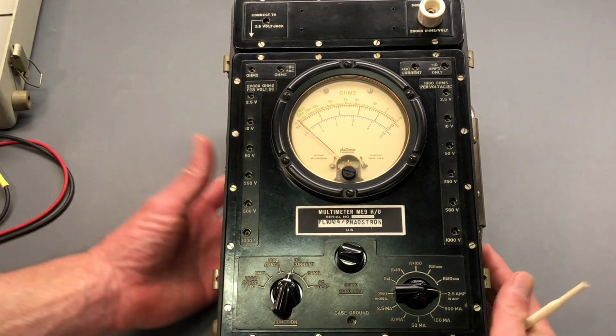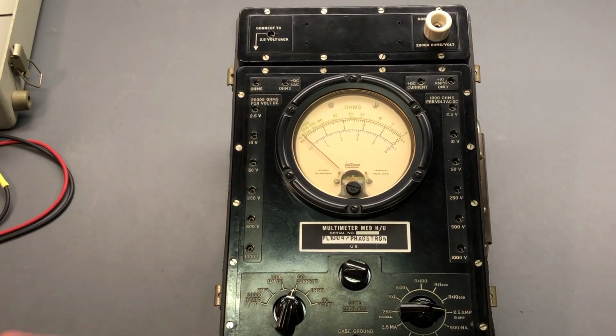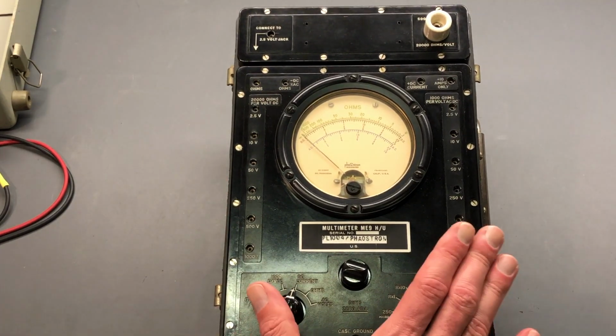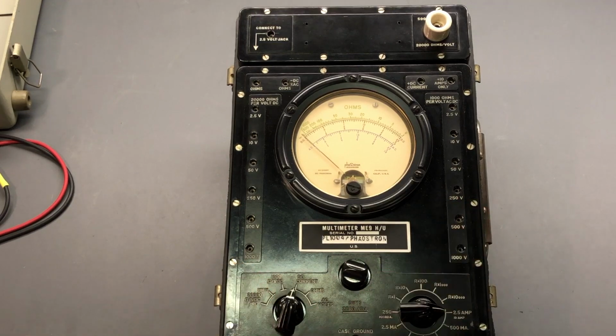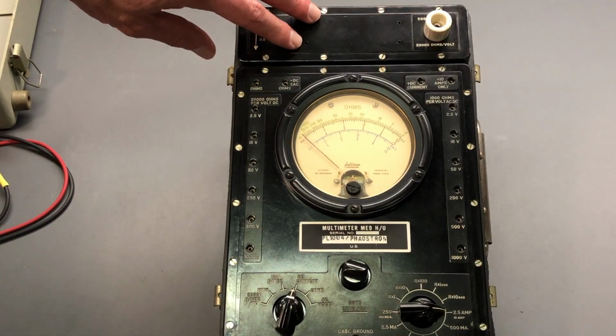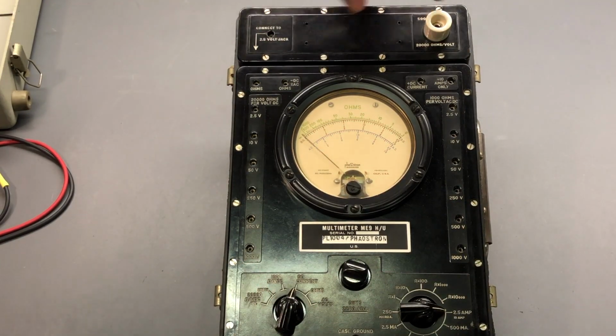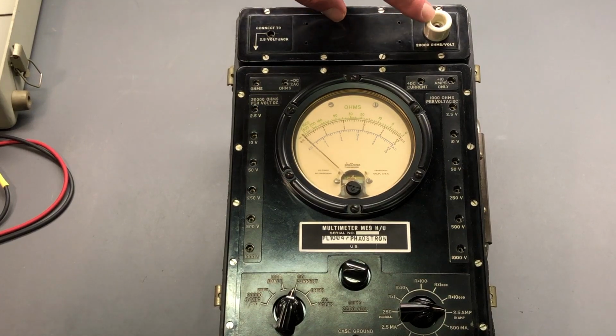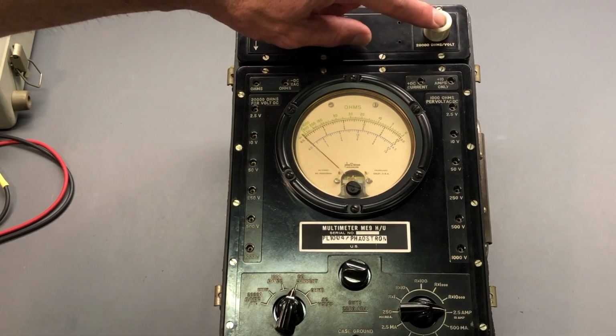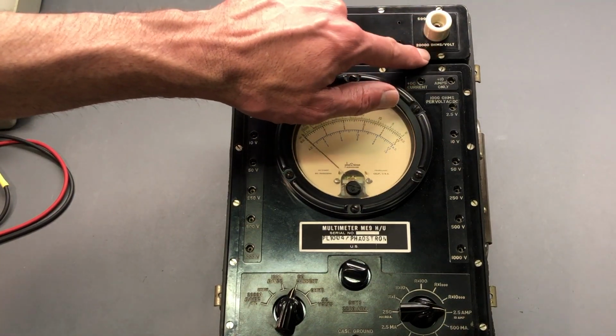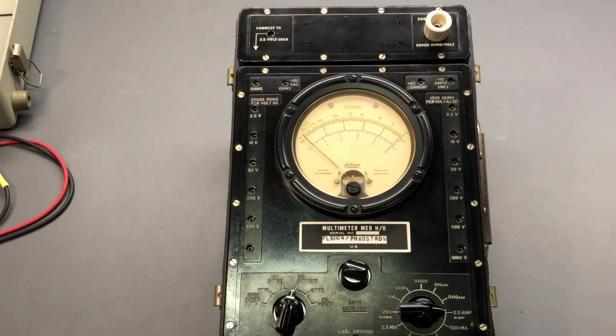Now at the top, I'll move this down just a little bit. This is optional. Not all of these ME9HUs have this, but on the top of here is a high voltage multiplier. We have a 5,000 volt input over here, which is actually just a standard banana jack input. You do want to use a high voltage probe, something that's rated for up to 5,000 volts. Common test leads are not rated that high. They often stop at 1,000 volts, so be cautious on what the test leads are rated, but you would need a special high voltage probe.